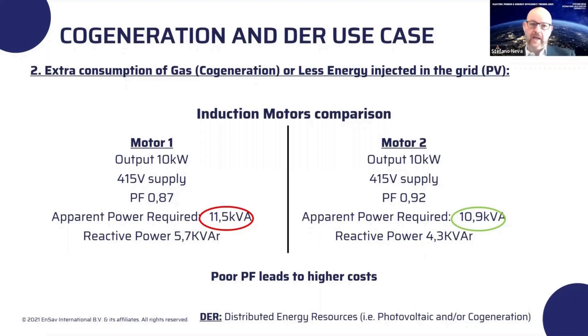If you see the comparison between two different power factors, by enhancing the power factor we are able to reduce the total apparent power needed, and therefore, generating this power locally, they will save gas. Normally you don't take this into consideration when relying only on grid sources, because the grid only makes you pay for apparent power if you have a bad ratio between active and reactive power. But when you're creating your own energy locally, this changes the entire perspective. So in this case, reactive power management is directly an energy saving technology. Next slide, please.